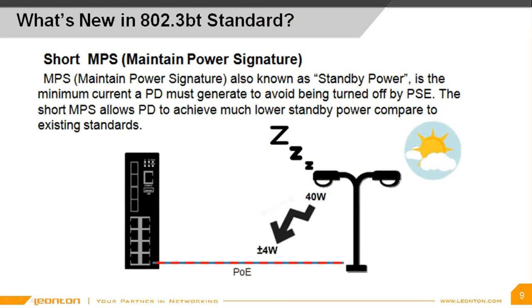The short MPS refers to the minimum power consumption drawn by a PD during standby mode in order to inform a PSE that the PD is still alive. Under the previous PoE standards, a PD had to draw power from a PSE at a 23% duty cycle, meaning the PD is on 23% of the time but off 77% of the time, which leads to unacceptably large standby power if a large number of PDs, such as LED lighting, are deployed in an office building. Under the new standard, the duty cycle has been reduced to 2%, so standby power has been minimized by a factor of 10. In this example, the street lamp will only draw 4 watts during standby mode.